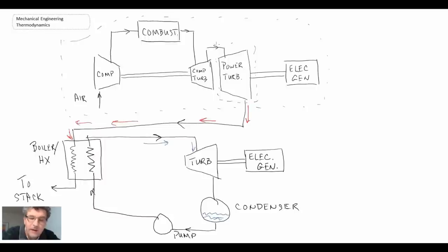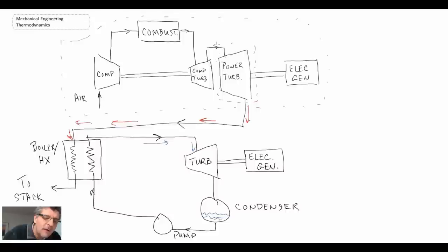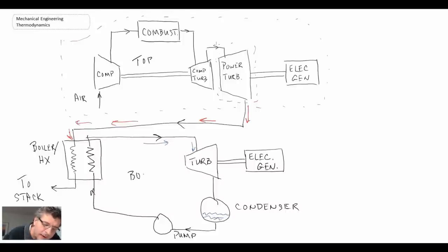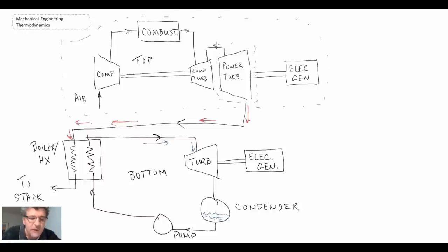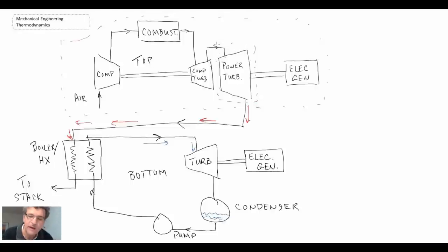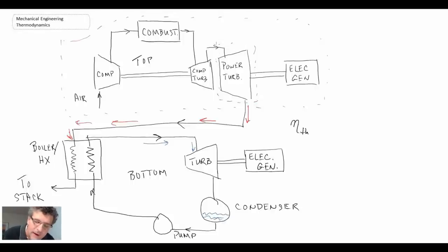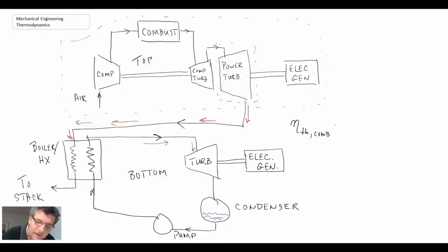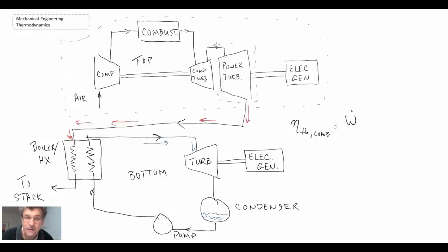So that's why we would call this the topping cycle, because it's at the top. And this would be the bottom cycle, because it's at a lower temperature in terms of the temperature of the exhaust gas coming out. Now when you have this combination, you do get enhanced thermal efficiency. And that's why it is a good type of cycle to use. It's a little more expensive, a little more complex. And the power outputs from the gas turbine are usually lower than you get from a normal vapor power cycle or a Rankine cycle.